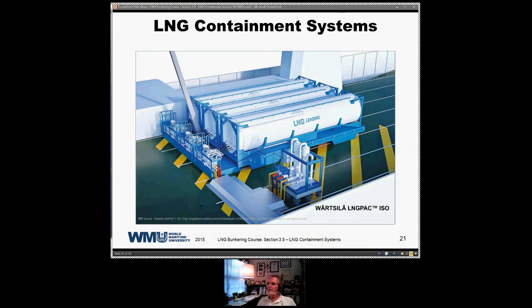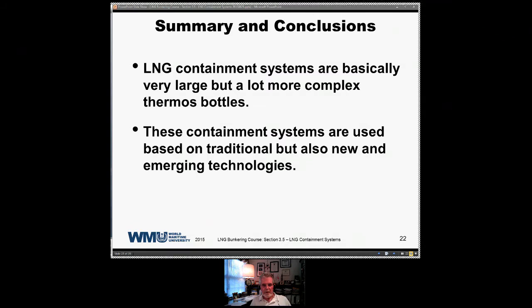The LNG containment systems are basically very large. They're a lot more complex. But they're a big thermos bottle, basically, is what it is. It's easier to compare a spherical tank with a big thermos because it's a round thing and it has insulation around it and whatever's inside is kept cold. And these containment systems are used based on traditional but also new and emerging technology. There are new types of insulations being tried by GTT and others to reduce the boil off that LNG carriers are subjected to. You have to allow the cargo to boil to keep the cargo cold, but you want to be able to minimize that boil off because every bit of gas that's produced in boil off has to be disposed of in some way.